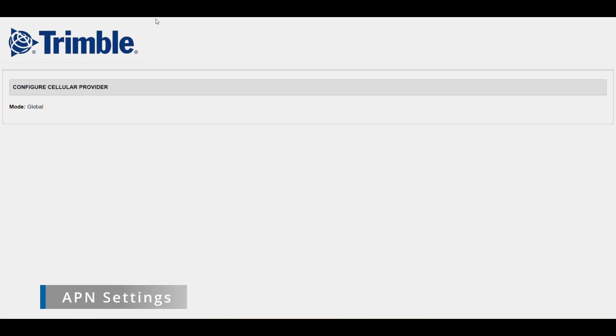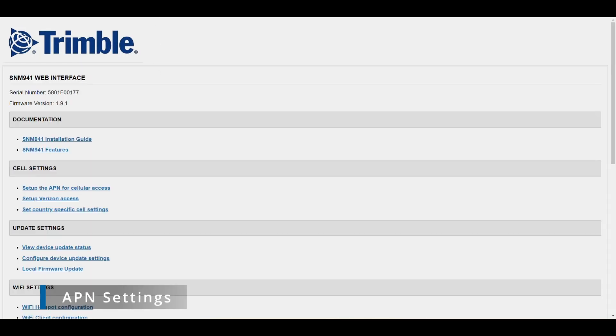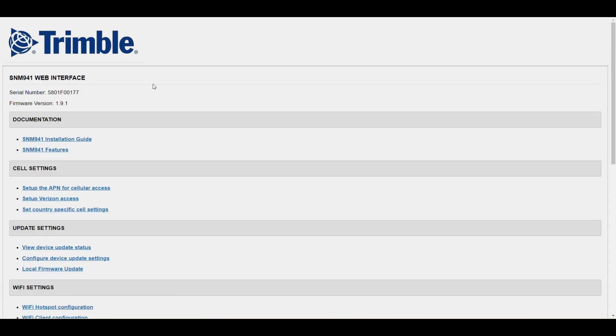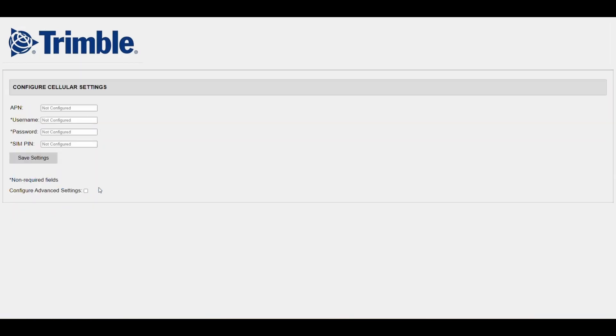The APN configuration is needed for the SNM 941 to be able to access the internet via a cellular carrier. This can be configured under cell settings, set up the APN for cellular access. Here, the correct APN for the carrier and the service can be entered.